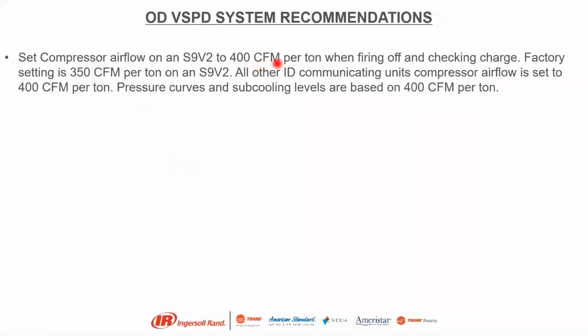S9V2 must be set at 400 CFM per ton when firing off and checking charge. That's a must. Make sure if we're doing an S9V2, we have to change that to 400 CFM per ton, because factory default's 350. It is possible we go out on head pressure because we're only running at 350 CFM per ton if it's not moving enough air.